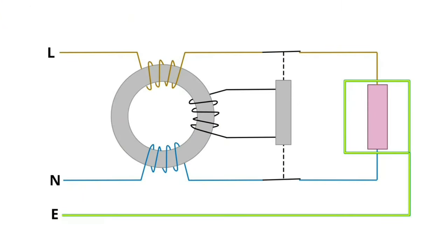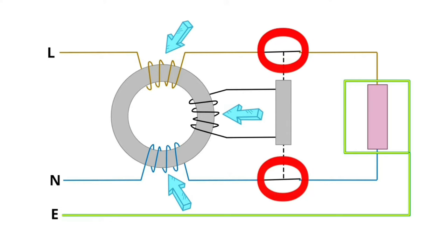But back to our question, the difference between an RCCB and an RCBO. Well, first of all, let's think about how an RCD works. We've got a diagram here of an RCD, which is the basic device that we've mostly been installing for years and years. Inside the RCD, the line conductor wraps around this toroidal or ring-shaped piece of soft iron. It then goes off and feeds the load. The neutral from the load then returns and wraps around the other side of the toroidal core and returns to the source of supply. Now, at the same time, wrapped around the core, there's this third coil that feeds a tripping device that connects to the switching contacts in the line and neutral connections.